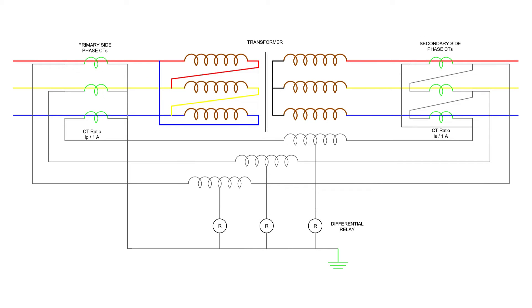Suppose you have a transformer which has primary rated current IP and secondary current IS. If you install a CT of ratio IP/1A at the primary side, and similarly a CT of ratio IS/1A at the secondary side of the transformer, the secondaries of both CTs are connected together such that their secondary currents oppose each other. In other words, the secondaries of both CTs are connected to the same current coil of a differential relay in such an opposite manner that there will be no resultant current in that coil under normal working conditions.